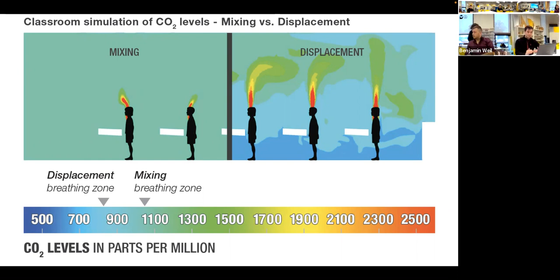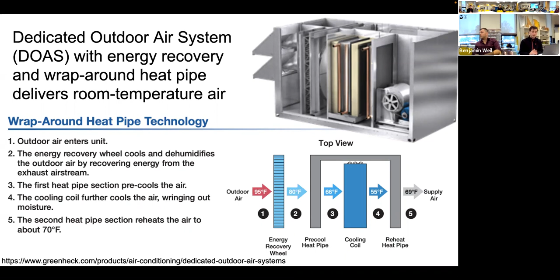We propose to use a dedicated outdoor air system with energy recovery and wraparound heat pipe that delivers room temperature air. The heat pipe starts by letting outdoor air enter the unit. Then the energy recovery wheel cools and dehumidifies the outdoor air by recovering energy from the exhaust system. Then the first section of the heat pipe pre-cools the air next to the cooling coil, further cools the air to get rid of moisture. Then the second section of the heat pipe reheats the air to about 70 degrees, which is the supply air.